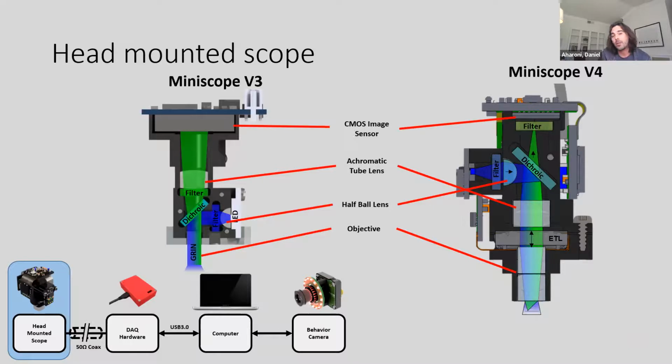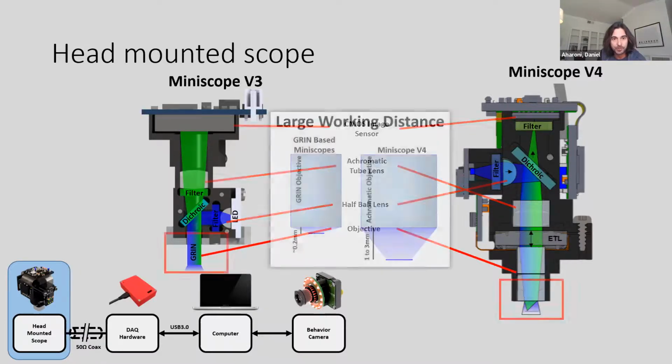And the optical path, which we'll see tomorrow, for the excitation light is important for some future work that we're currently starting now, where the excitation light goes through all the same lenses and optics that the emission green light goes through. And this gives us room to shape the excitation light to be more uniform, but it also gives us some abilities to do other fun things, which we'll see later. And then the optics just form an image on an image sensor. The newer generations, between the image sensor and the more optimized optics, are somewhere between 10 to 15 times more sensitive than previous generation miniature microscopes.